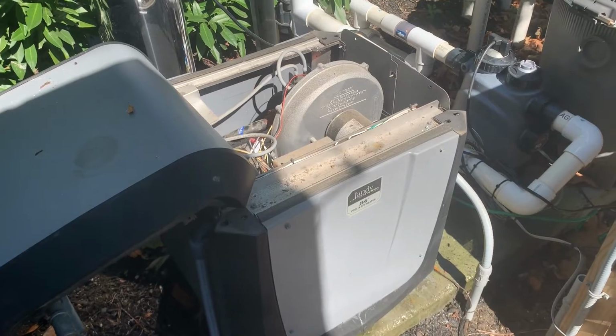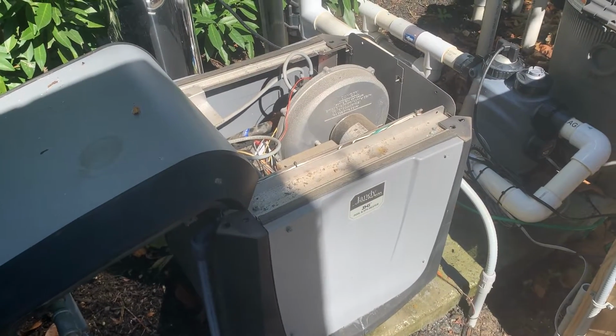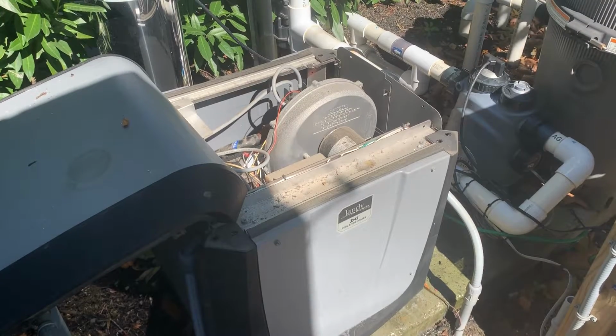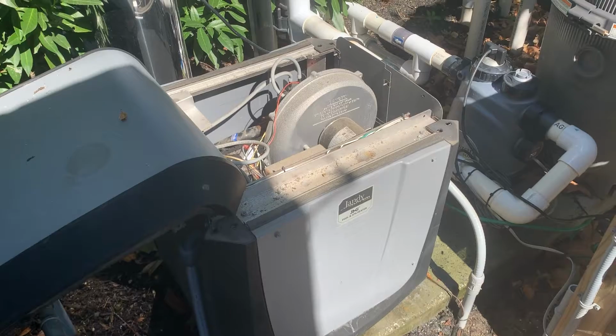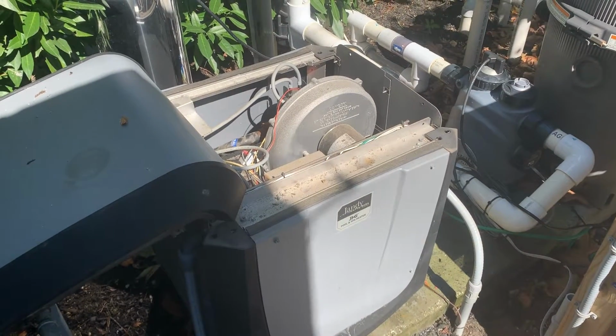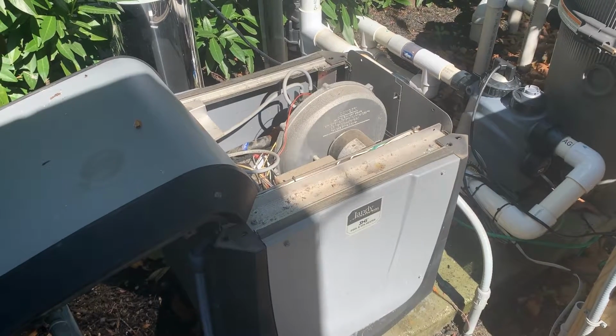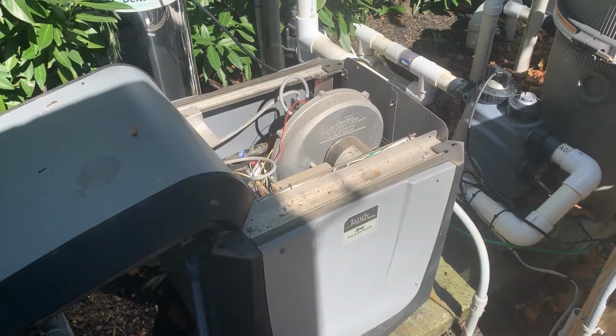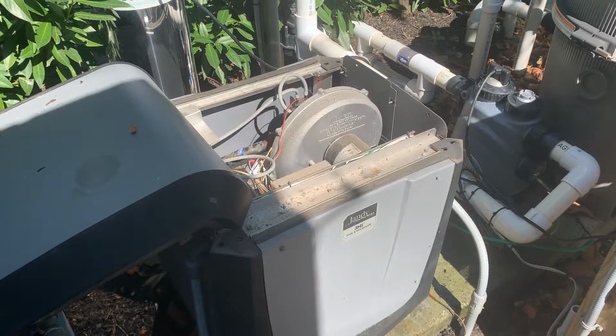Now, normally you would blame this on water chemistry, what have you, but it's not. Water chemistry is perfectly fine. It's always been maintained on a weekly basis. There's a weekly service that comes in. The pH, alkalinity, everything is always balanced perfectly, hardness, everything. But unfortunately, this JXI400 needs a new heat exchanger.